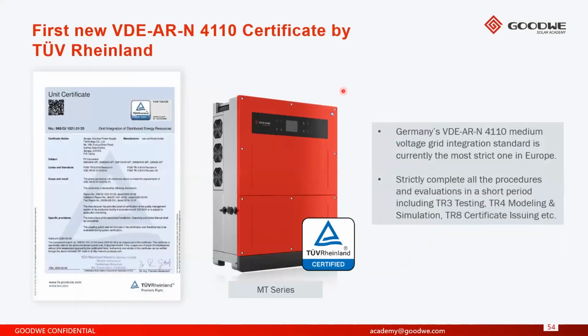We were the first inverter manufacturer to have the new VDE-AR-N 4110 certificate, which was released by TÜV Rheinland. So this is a German certificate, which is very difficult to get. Essentially, it is a certificate that you need to connect the inverters to the medium voltage and the high voltage network in Germany, and a number of countries in Europe also require inverters to have this VDE certificate to allow connection into the grid.